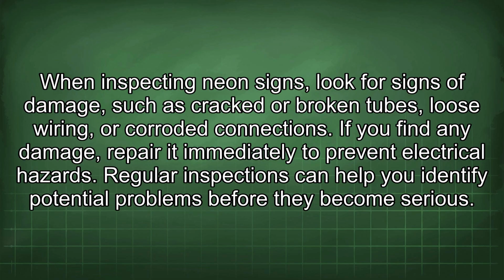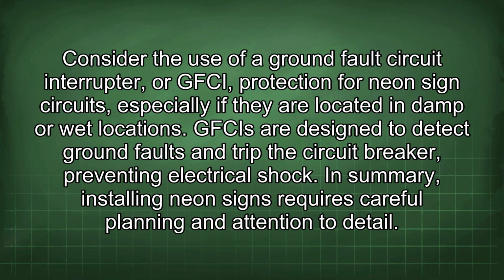If you find any damage, repair it immediately to prevent electrical hazards. Regular inspections can help you identify potential problems before they become serious. Consider the use of a ground fault circuit interrupter, or GFCI, protection for neon sign circuits, especially if they are located in damp or wet locations. GFCIs are designed to detect ground faults and trip the circuit breaker, preventing electrical shock.